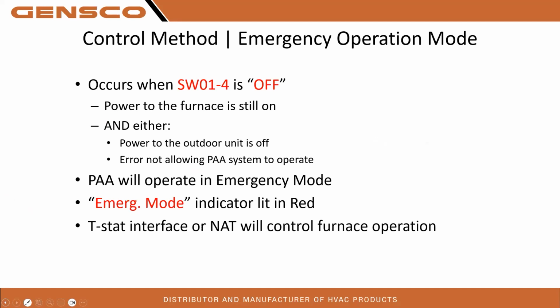Emergency operation mode. Again, what will happen is if a heat pump goes into default emergency operation, if something happens to the heat pump where it goes into an error code, loses communication, or sees that it's powered off, you won't need to do any dip switch changes on that. It will automatically switch over for you, and it'll be indicated by the emergency mode indicator lit up red. And at that point, either your 24-volt thermostat or your non-adjustable thermostat will control the furnace operation.